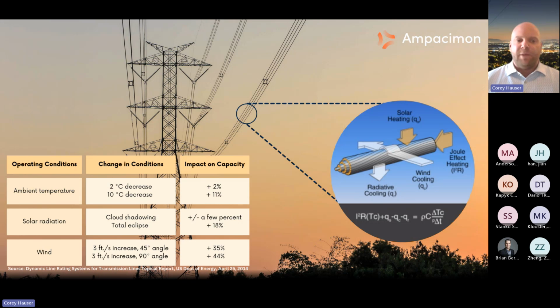It is by far and away the most massive factor that impacts the capacity on a line. As we see there, we have 3 feet per second, and that's no more than the wind you feel as you're walking down the sidewalk. So it's nothing that isn't there a vast majority of the time. And when that wind at 3 feet per second hits a conductor at a 45-degree angle, you're looking at about a 35% increase in capacity. And when that switches to hitting the conductor directly perpendicular, it can go up to 44%.